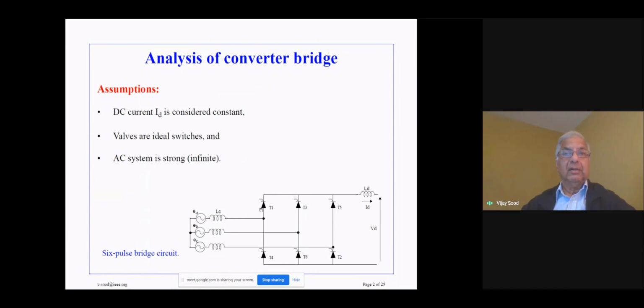So this is the basic HVDC converter bridge. We have the DC voltage indicated as VD, the current ID. LD is the smoothing reactor, which maintains ID as constant. It's a fairly large value. We can assume that it's a large value, so therefore the DC current does not change very much. LC is the commutation inductance. Usually it is of the order of 15 to 18% of the transformer, which could be connecting these AC system to the DC system.